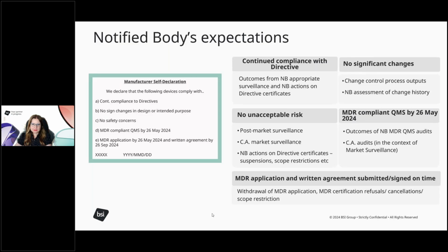The fact that the QMS should be in compliance with the MDR requirements can be impacted by the outcomes of the audits conducted by the notified body, as well as by audits conducted by the competent authority in the context of market surveillance. And finally, the condition of having applied for an MDR on time or having a written agreement signed on time can be impacted, as we just saw, by withdrawal of the MDR application by the manufacturer or refusal to issue the MDR certificate, cancellation of the MDR certificate, scope restriction.